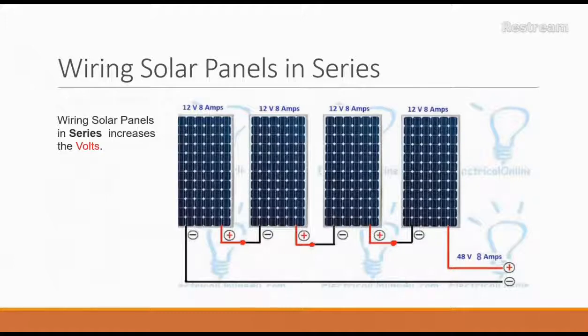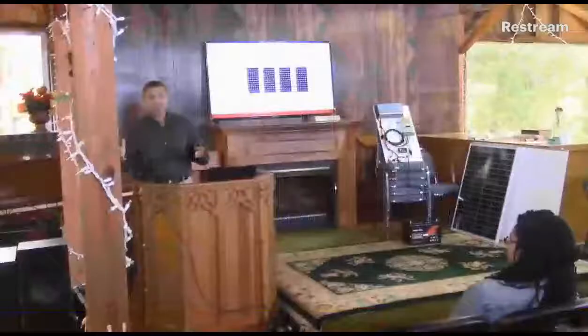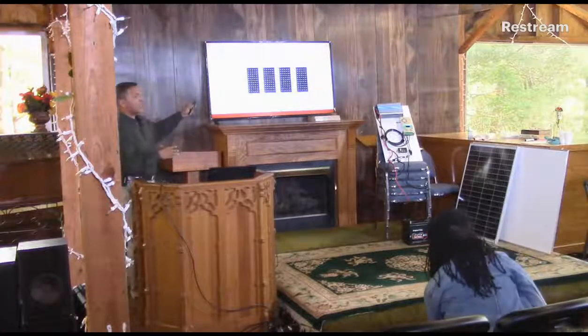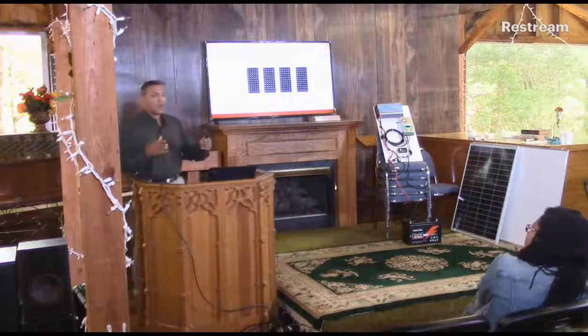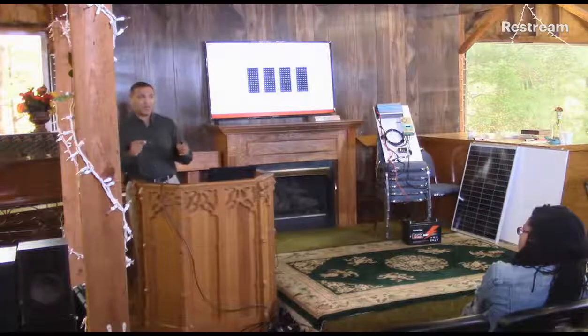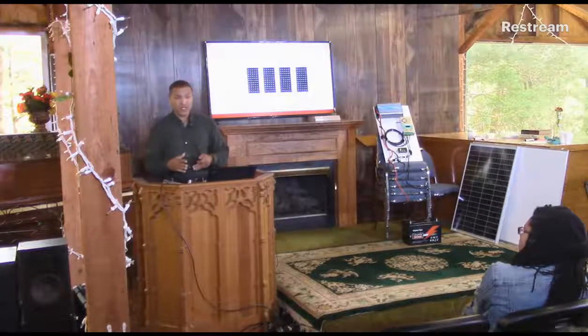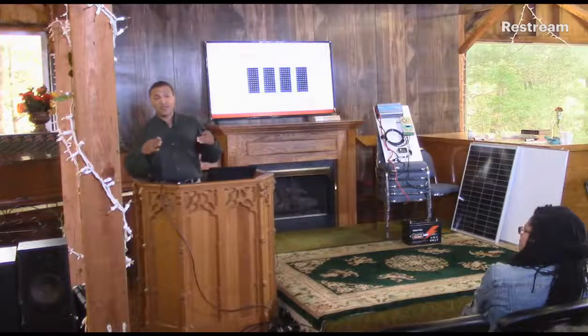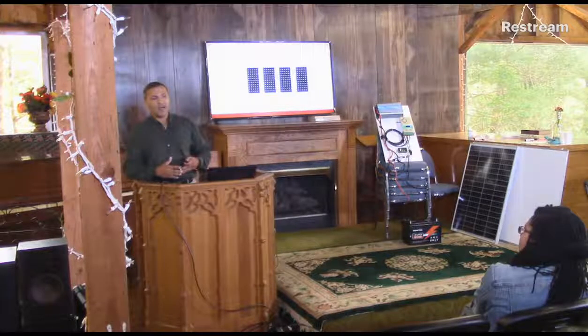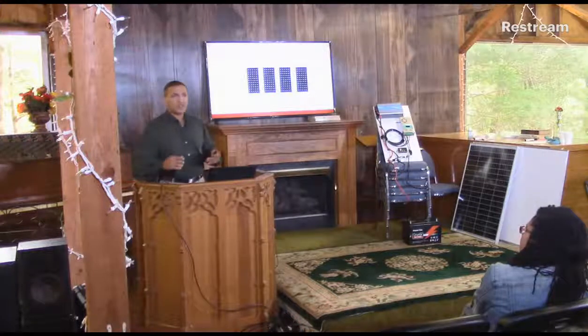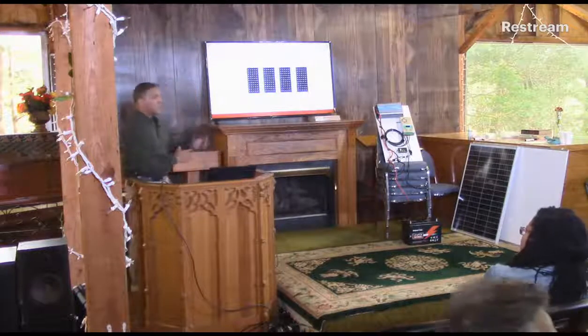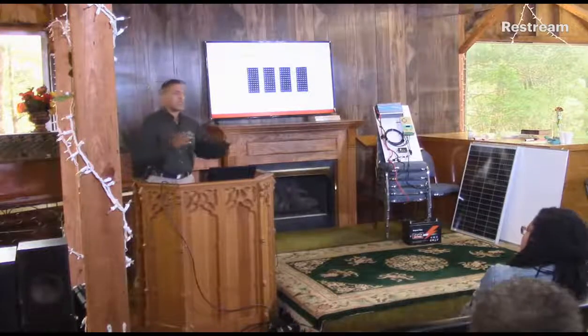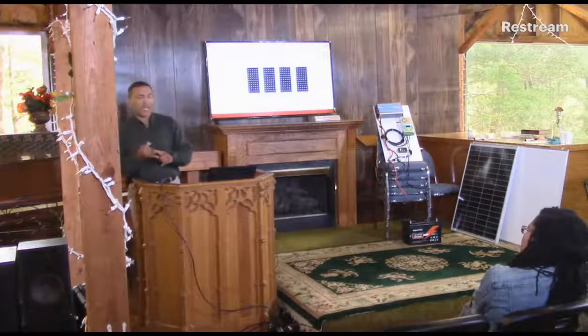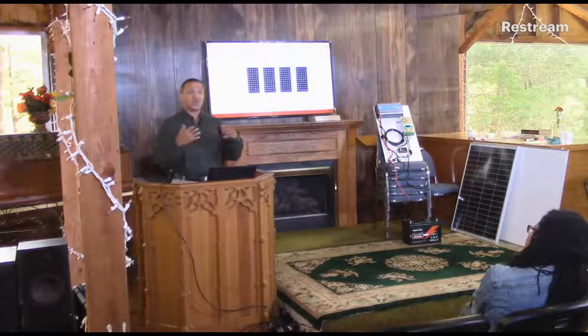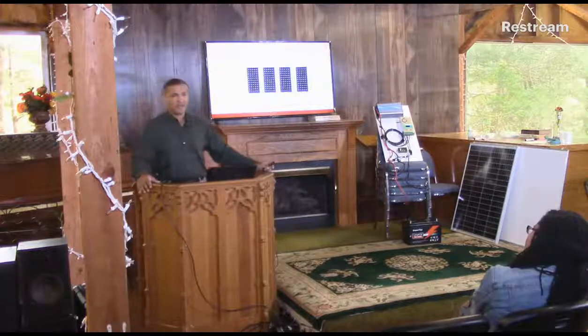Now they range in the voltage for that. Some of them range from at least 12 volts on up to 120 volts. But in your sizing of your panels, you have to make sure that you know what the manufacturer requires for that piece of equipment. Because if that piece of equipment says I can only put 250 volts through it, and you put 252 or 260, you're going to fry that charge controller inverter. So it's important to know the right amount of voltage. So in wiring the panels in series and parallel, it gives you the right amount of amps and the right amount of volts to put through that inverter. So it'll be efficient. Okay, we may have to discuss it later.